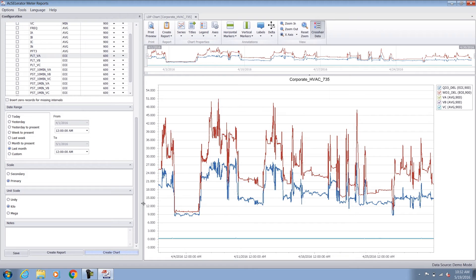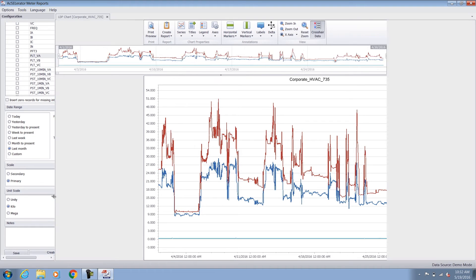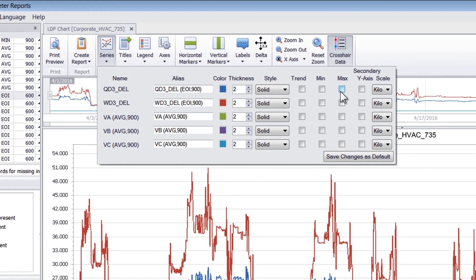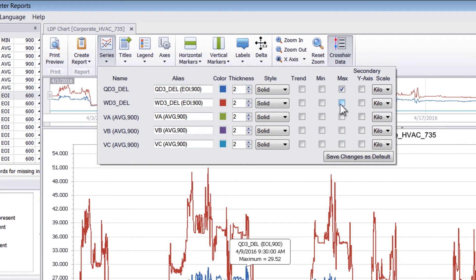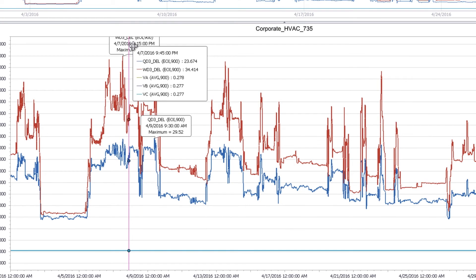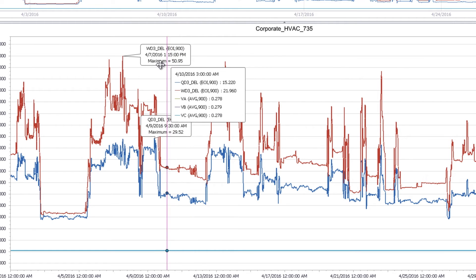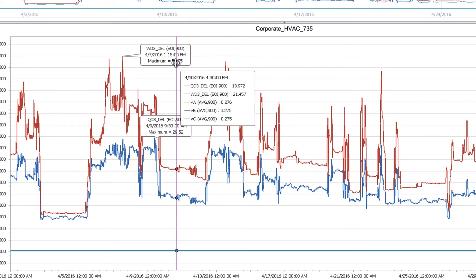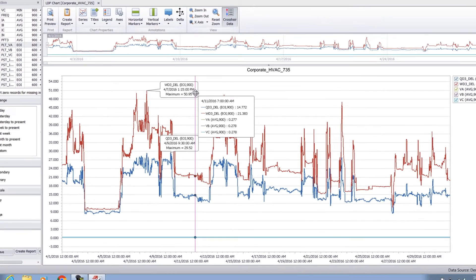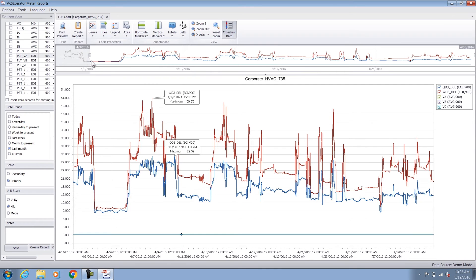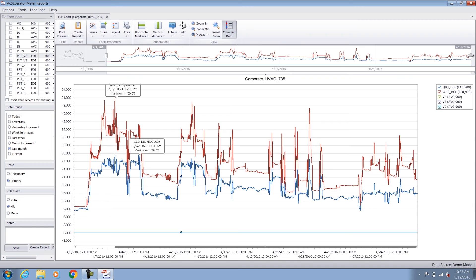I'll start with the create chart option and see the data. Here you can see a trend of the demand quantities for a period of one month. To find the absolute peak of this, I select series and then the max checkbox option. The annotations on the screen then tell me that the max peak demand occurred on 7th April at 1:15 PM and the maximum recorded was 50.95 kilowatts. I can use the time scroll on the top of the screen to zoom in to an area which I want to focus on.